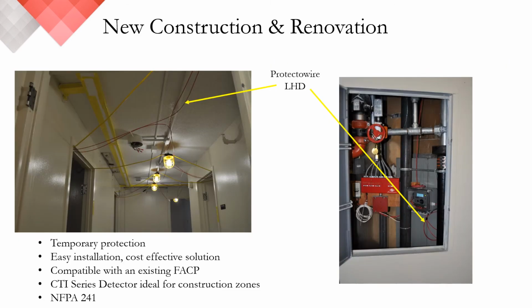We've all read the stories of a construction project or renovation that suddenly caught fire. There are a number of reasons for the causes: hot works, improper disposal of smoking materials, or even cooking lunch in non-designated areas. In many cases, an active alarm panel is on site, but the smoke alarms and sprinkler systems are taken offline to avoid false alarms. This leaves the contractor and facility owners with the responsibility to provide 24-hour fire watch.